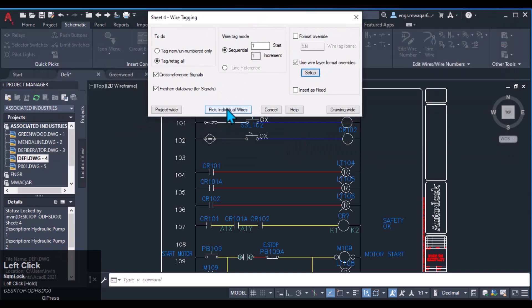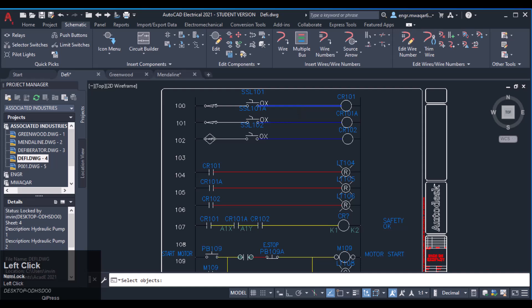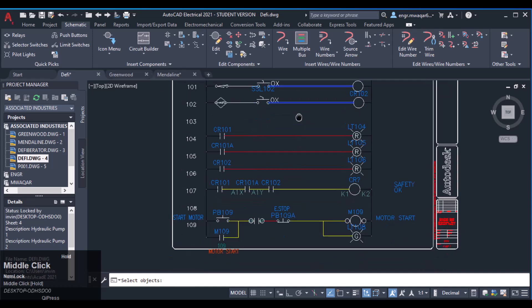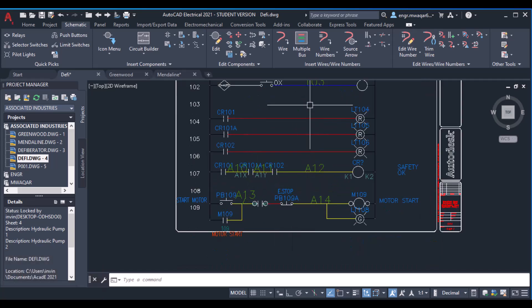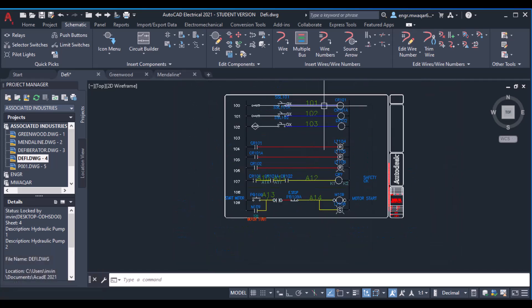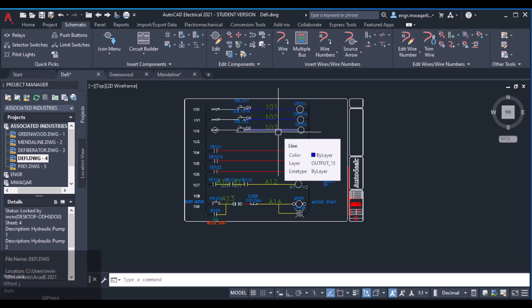To apply the override, check 'Pick individual wires' and check the box to override the wire layer format. Click OK, then select the yellow wires and click OK. You can see the wire numbers have changed — 101 is our default layer and the yellow layer wires now show a different format. In this way we assign different wire numbers to different layers, easily dividing the whole drawing into different sections with different numbering formats.